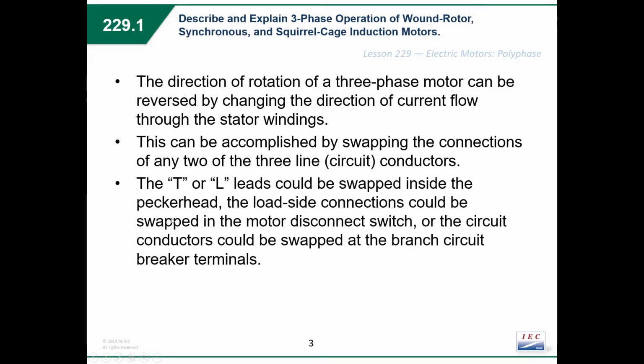So you could rotate your T or L leads on the motor itself. Usually, most times you're going to do that maybe at a breaker panel, or most commonly, I would say, at a disconnect. You have a little more room to work inside of it. Think about a disconnect. But either way, swap any two of the line wires at basically any point that is convenient.